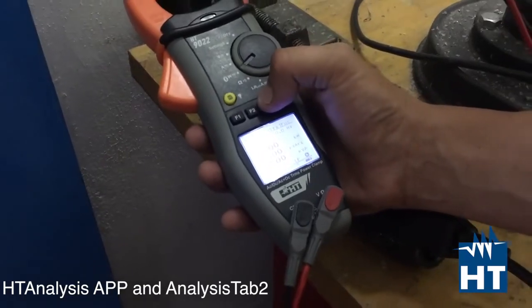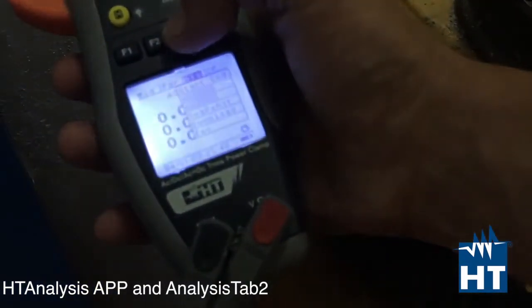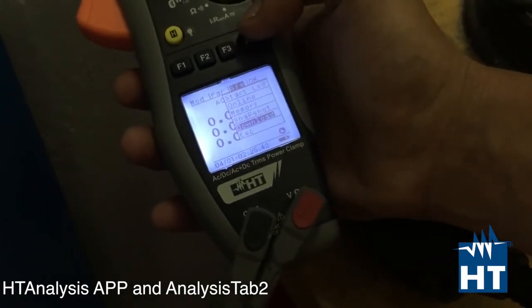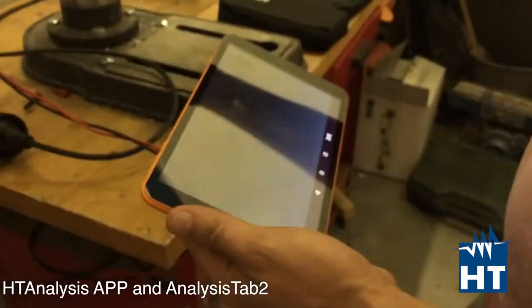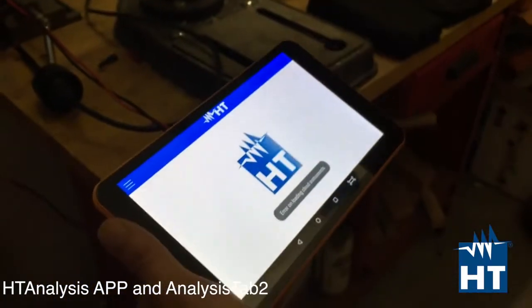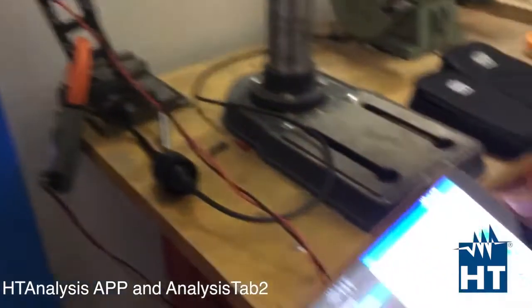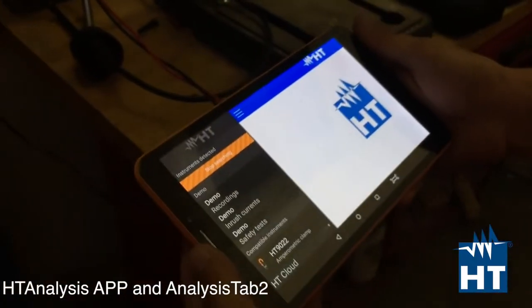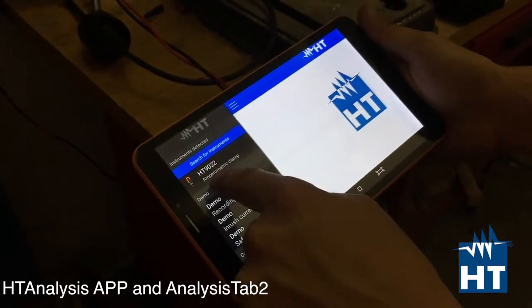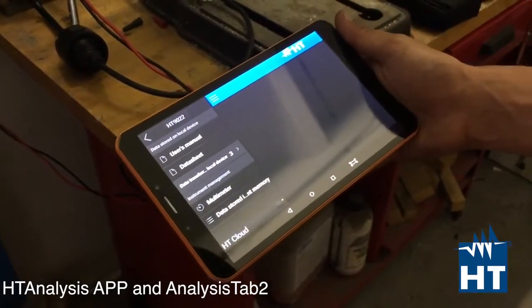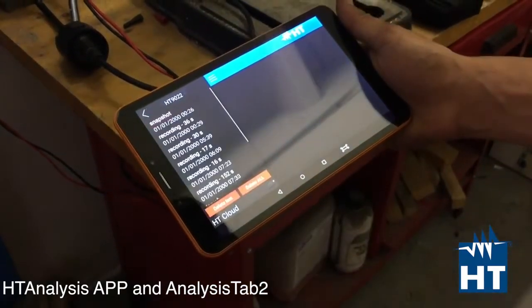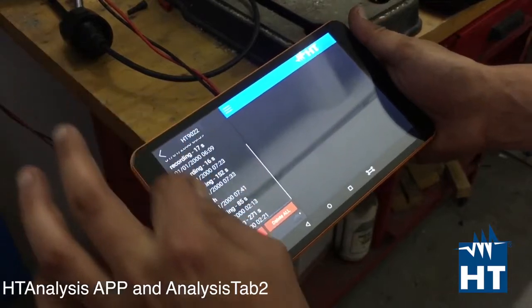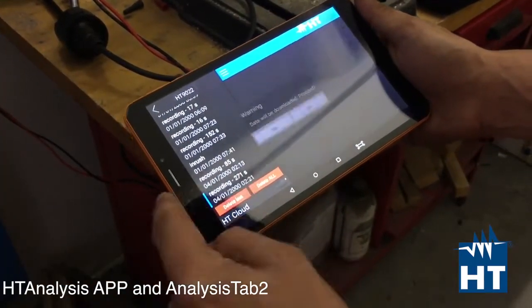So to download data, simply go to system again and put the instrument on download. Okay? Then we're going to see the results on the HT tablet. This allows you also to work in a very dangerous environment, so you can be far away from the measurement point where the danger is. So you're going to see search for instruments. We're going to find 9022, and we're going to click on it. And we're going to see data stored in internal memory. Click it and you get several recordings. So we're going to take the last one and download it.